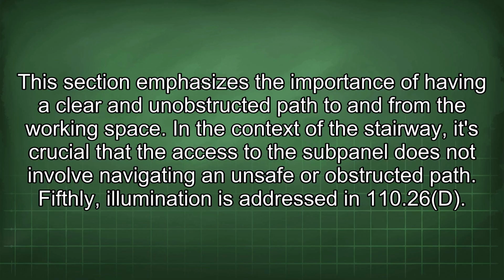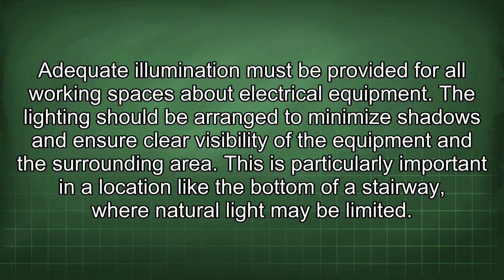Fifthly, illumination is addressed in 110.26d. Adequate illumination must be provided for all working spaces about electrical equipment. The lighting should be arranged to minimize shadows and ensure clear visibility of the equipment and the surrounding area. This is particularly important in a location like the bottom of a stairway, where natural light may be limited.